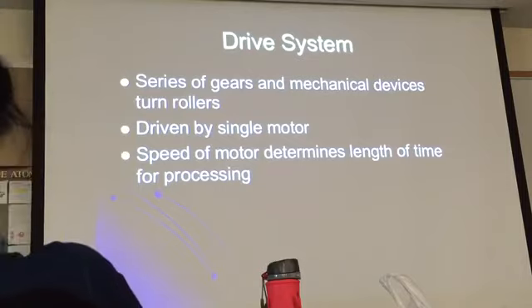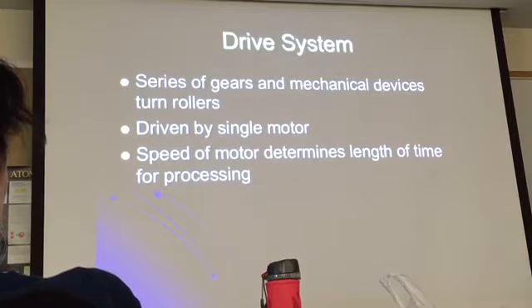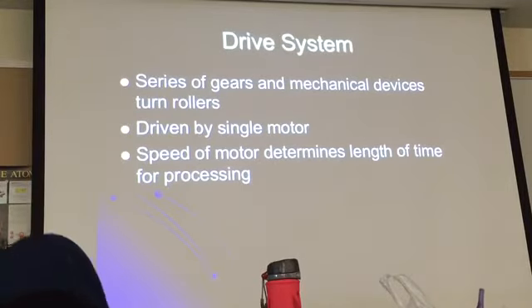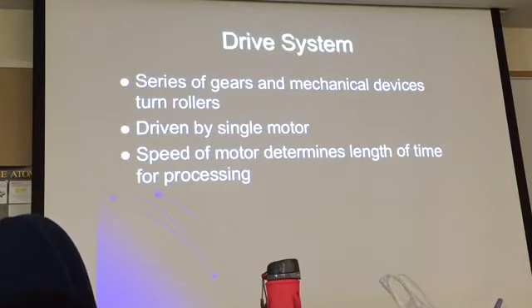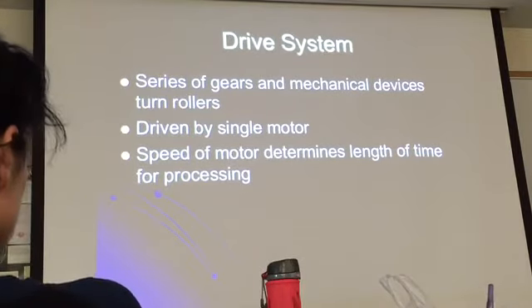The speed of the motor determines the length of time of processing. You can change the speed depending on the type of film and the type of work you do. For example, mammography film — you need to keep it longer. The typical 90-second film processing becomes about two minutes for mammo, because you want the film to be very contrasting, very black and white.